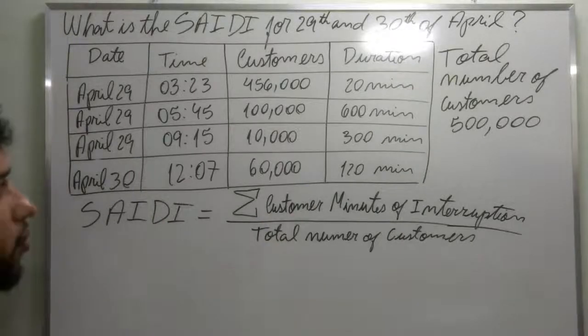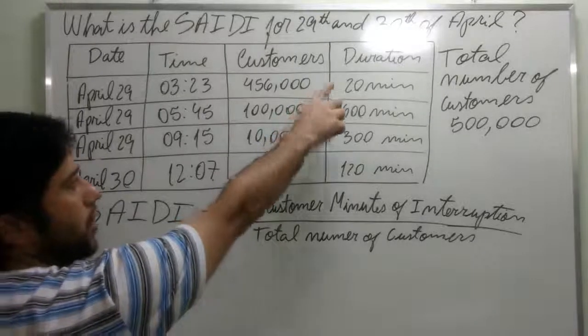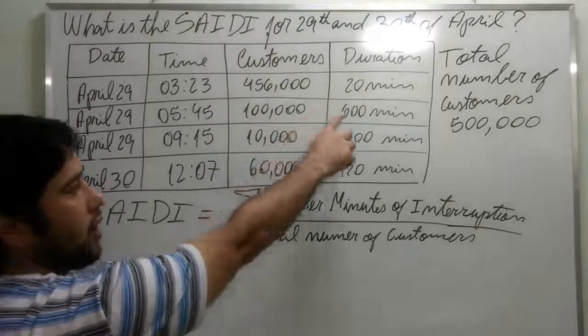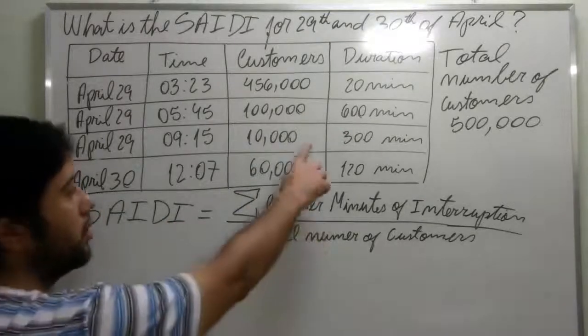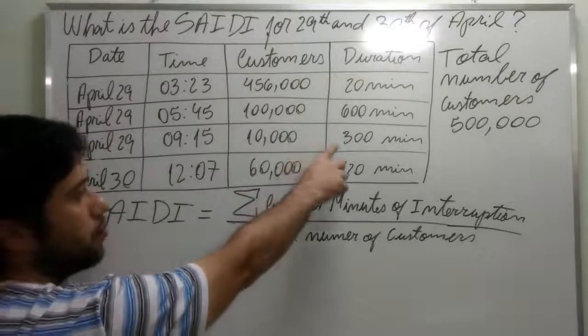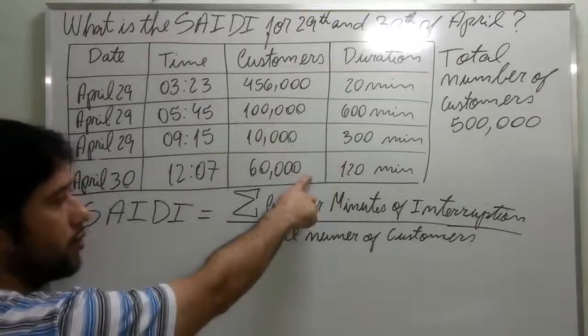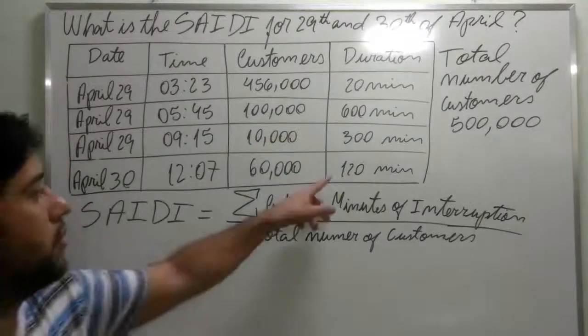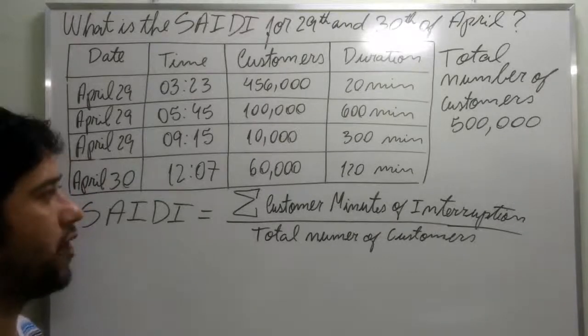Our SAIDI is going to be 456,000 times 20 minutes, plus 100,000 customers times 600 minutes, plus 10,000 customers times 300 minutes, plus 60,000 customers times 120 minutes — all divided by 500,000.